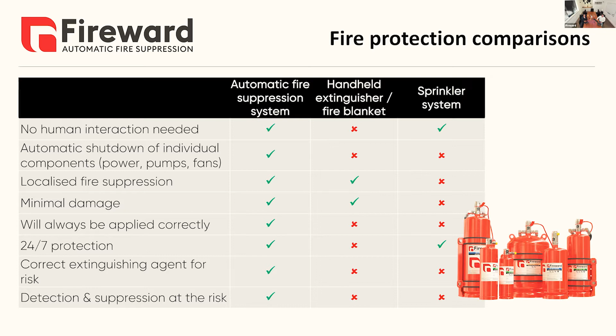That's a key part of what we do: often operators with systems fitted don't really understand they've had a fire, because the fire system has already gone off long before they've seen flames in a typical manned bit of kit like a wheel loader shovel or an excavator. Yeah, and that table really confirms that point, that it will always be applied correctly because it's detecting and suppressing in the actual hazard itself. And it will give 24/7 protection. A massive difference from the portable side. And as you can see, by the time the guy's seen that very big fire, our system's done its job and he's coming in later on. So you can see the time differences.